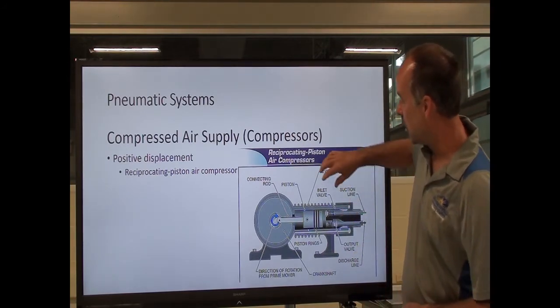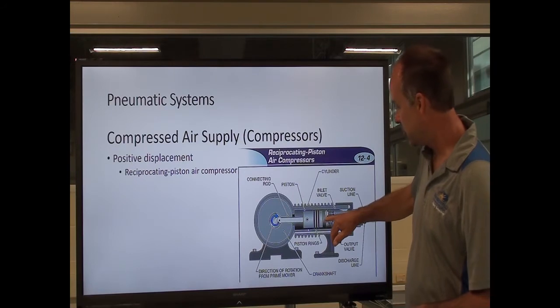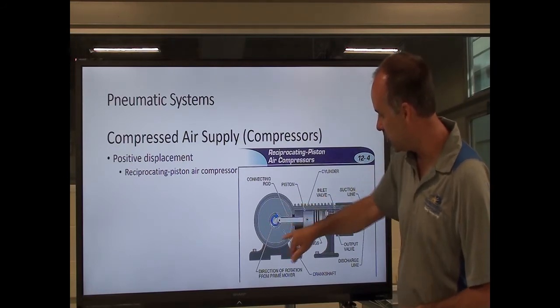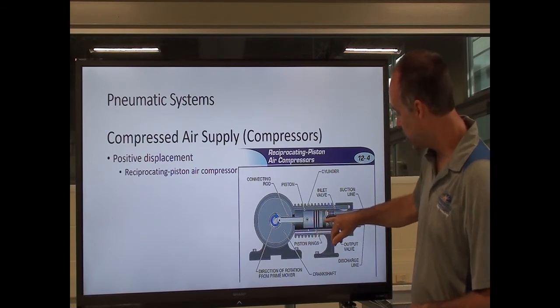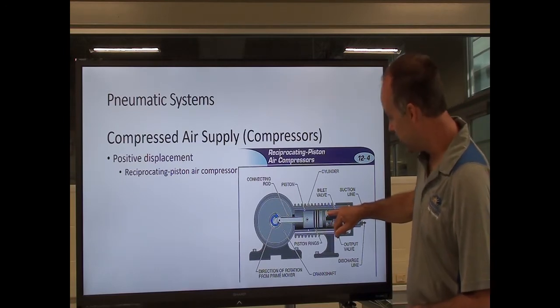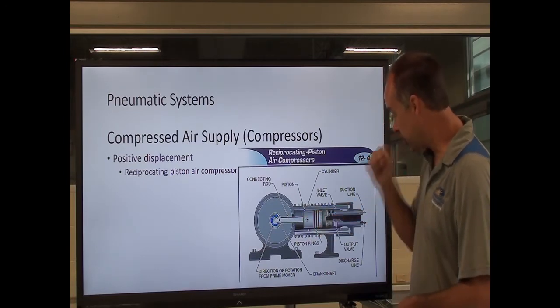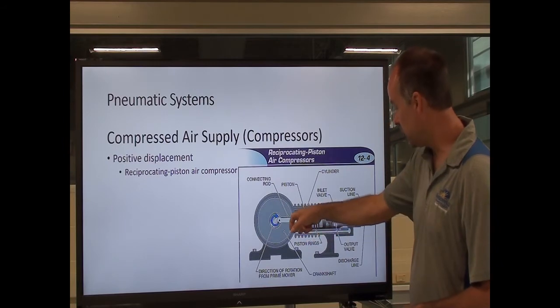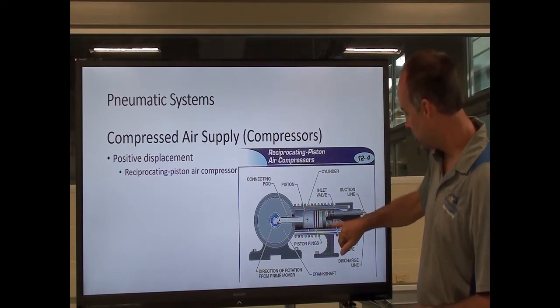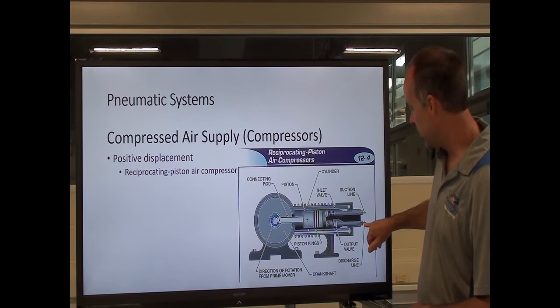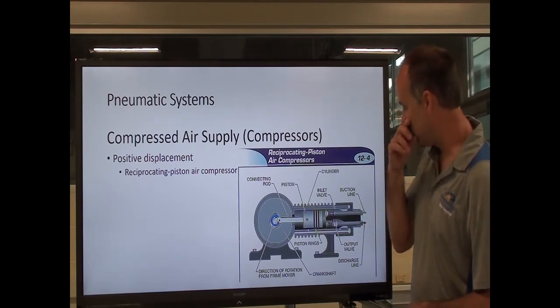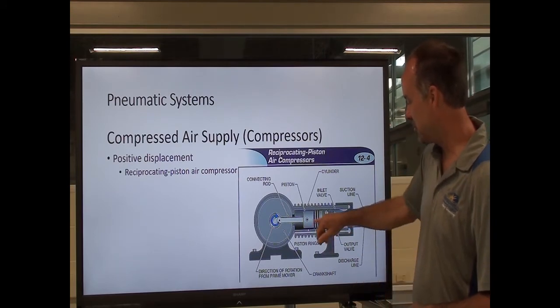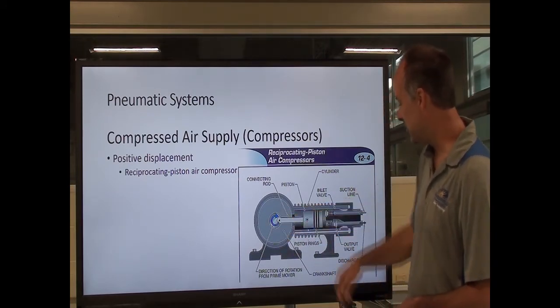A reciprocating piston compressor — essentially when the prime mover is spinning, it's pulling the piston in and out. As the piston draws back, you open the intake valve and allow air to be drawn in. When the piston comes back out, that valve closes and the other one opens, allowing compressed air to be sent to the receiver. It's much like an internal combustion engine, except instead of the piston driving the crank, the crank is driving the piston.